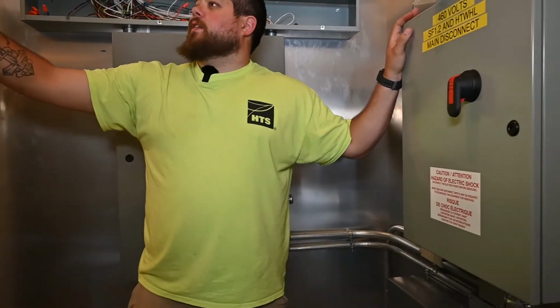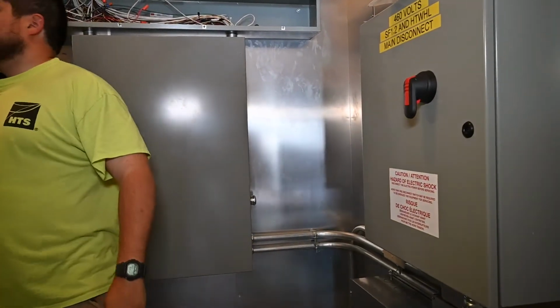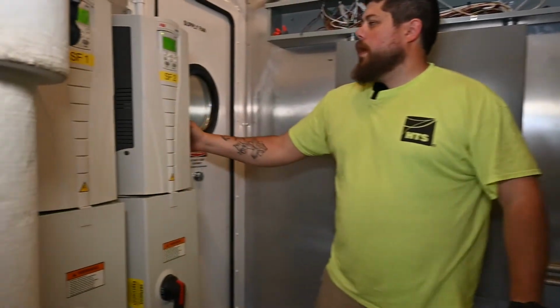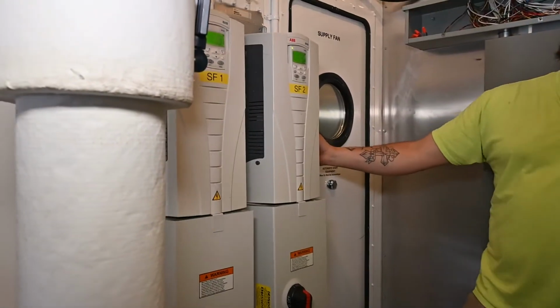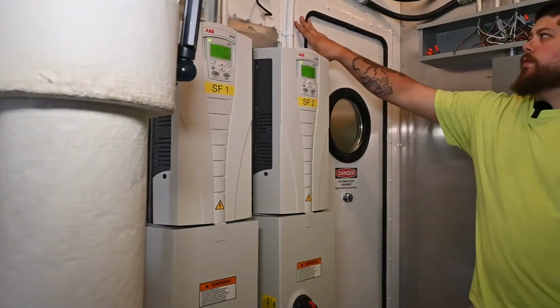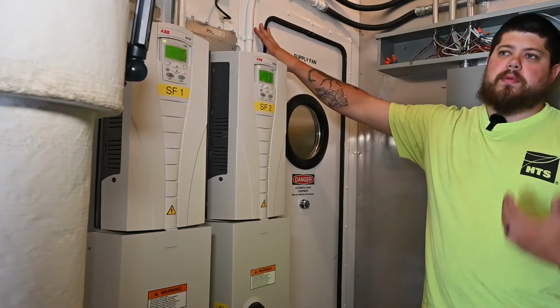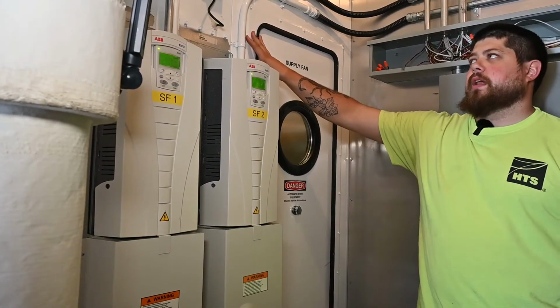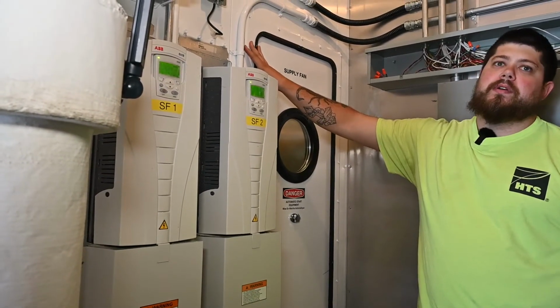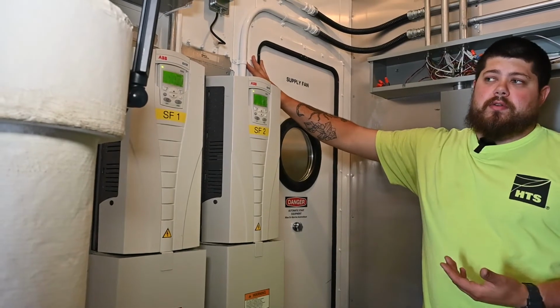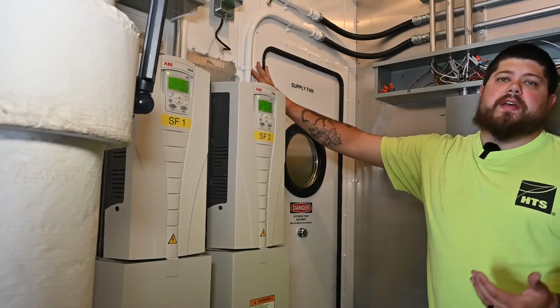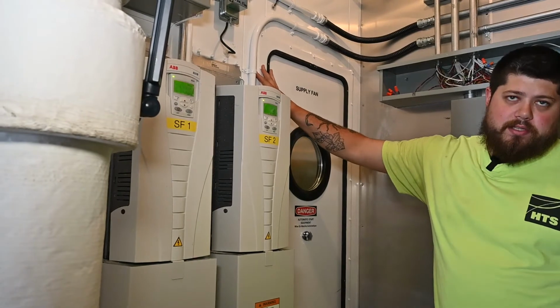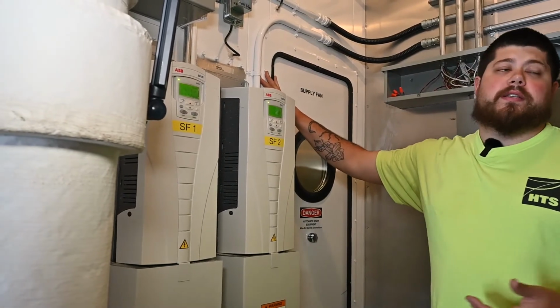Another nice thing I like to mention is the design of the doors. As you can see on this door, it closes in, and there's a flange on the outside. This is just basically to tell you that this is going to be a positive section. This is to allow it so when you open it, the door does not come and hit you. On the inside, you will notice that the door is closed from the inside against the groove. That is because that is going to be a negative section, and that'll stop the door from actually pulling into the other section.